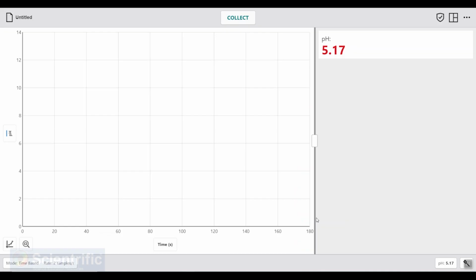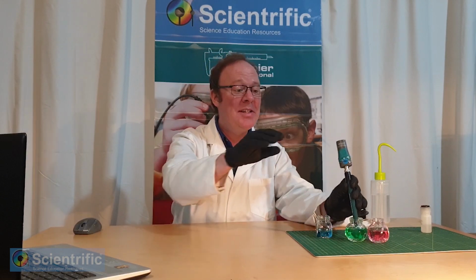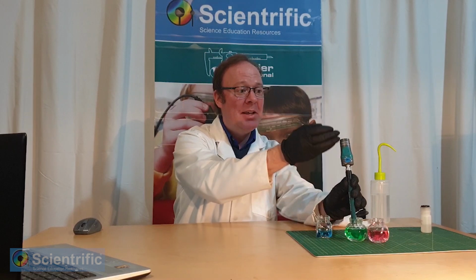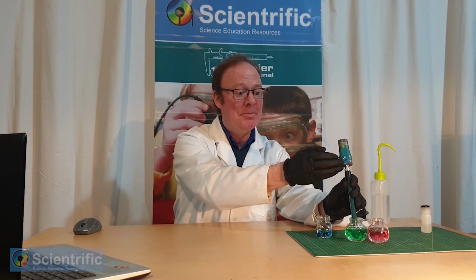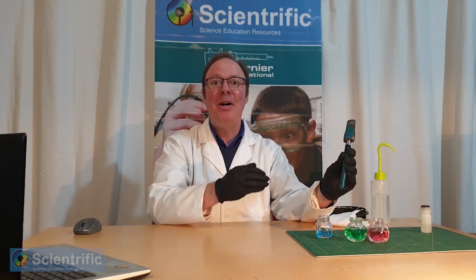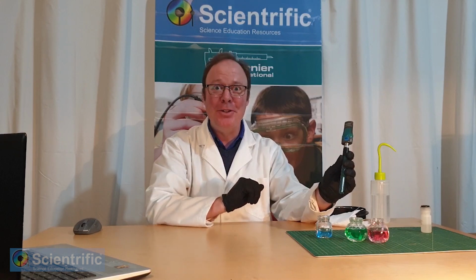Now that I've done that, all I need to do is hit Apply. There you go. We have it calibrated. The calibration itself is stored inside of the transmitter module up here. Now my Vernier pH probe is ready to use.